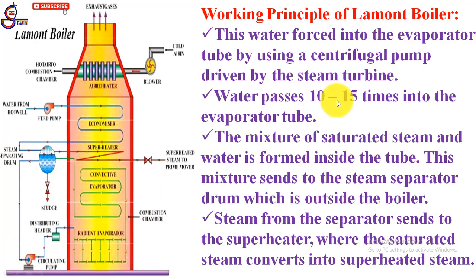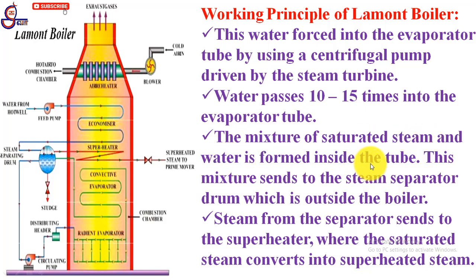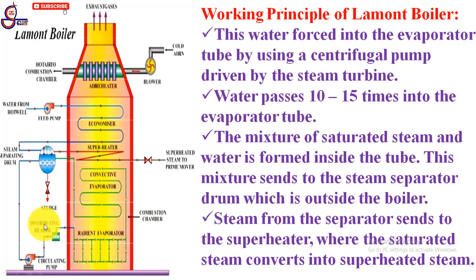Water passes 10 to 15 times through the evaporator tube. The mixture of saturated steam and water is formed inside the tube. This mixture is sent to the steam separator drum, which is outside the boiler, containing a mixture of saturated steam and water particles.